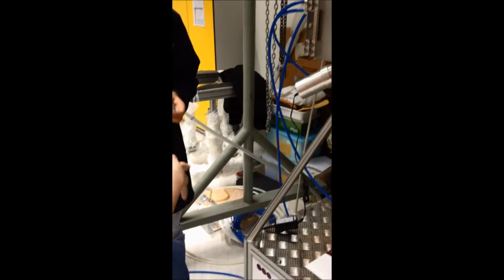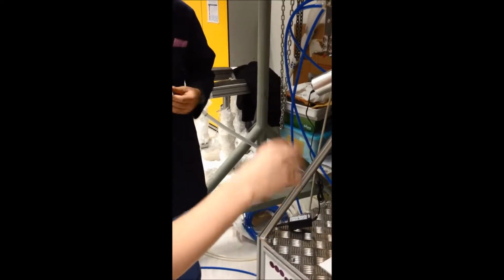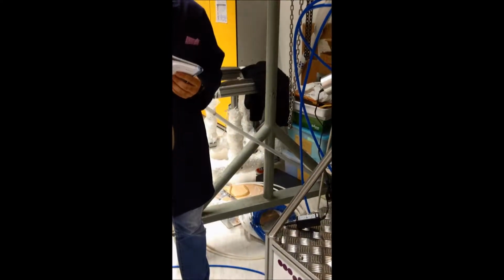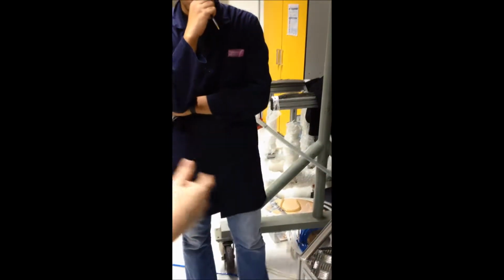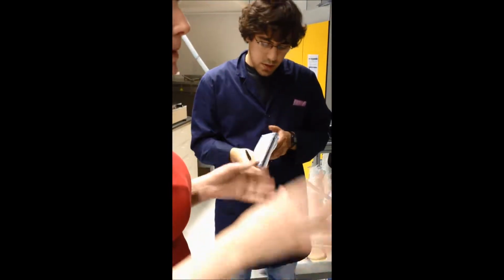The problem I was having when using the chiller was with the temperature, not the flow — the flow was fine. When I was running this at 800 degrees, the water got so hot that it cut out, because there's a set point on the chiller. It cut out, and because the water stopped, the power supply stopped too, because of the interlock.